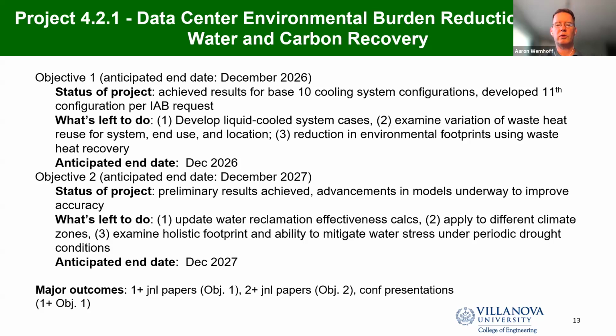Once we have that, we'll apply it to different climate zones. So in the ASHRAE climate zones where we have representative locations, we're going to use the TMY3 database to look at, for a given climate zone, what would be the overall annual water reclamation capability for each of our different types of cooling systems that we're modeling.